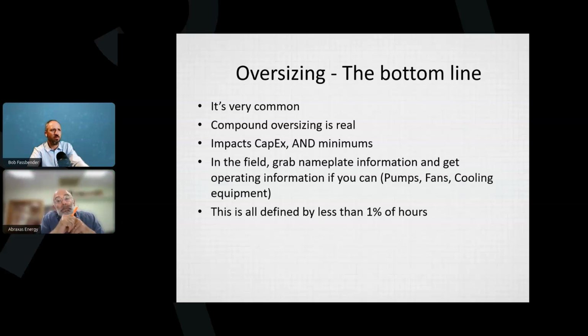No. Okay. No, I mean, you might want to figure out what the brake horsepower is on that pump, because it's probably not operating at, that comes out to 74.6 kilowatts, right? Right. And if you're actually modeling it, you might want to figure out what the real brake horsepower is. It'd be great if you had meter access. You probably don't, but you could do a conversion. You could ask ChatGPT what that is, rather than me explaining it, but it's not an oversizing problem. So oversizing isn't an issue in this case then. No, there's nothing you can do about it.